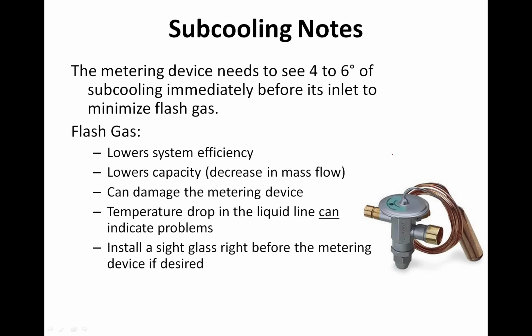Most of the time, you don't have to do that unless you suspect a problem. It's a very easy way, by adding that port in there, to just make sure your liquid line's not undersized or kinked or there's a problem with it. If we don't have that subcooling, we're going to get flash gas. And flash gas simply means that the refrigerant has dropped down to a saturation temperature, and now it's no longer subcooled. It's not 100% liquid. It's actually a mixture of liquid and vapor. And that flash gas lowers the system efficiency.